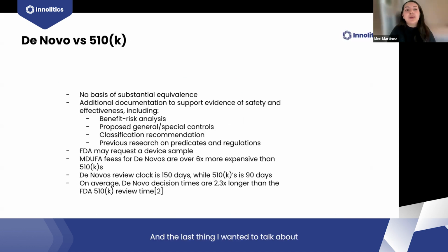And the last thing I wanted to talk about is just the key differences between de novos and 510(k)s. Because de novos are for new types of devices, we're not comparing ourselves to anything else, so there's no wording nor documentation around any basis of substantial equivalence. Instead, you're providing evidence that your device is safe and effective on its own. And some evidence for this includes things like providing a benefit-risk analysis to describe how the benefits of using your device outweigh any risks associated with it.